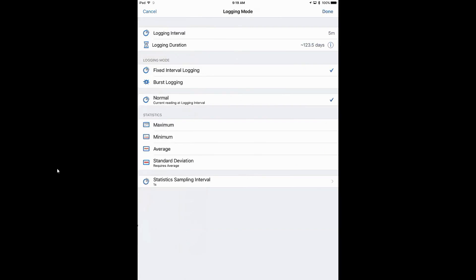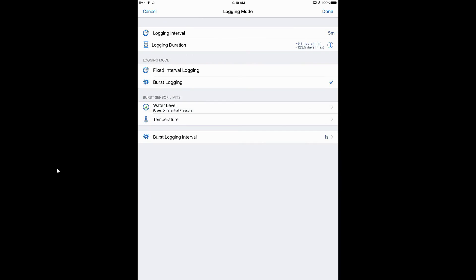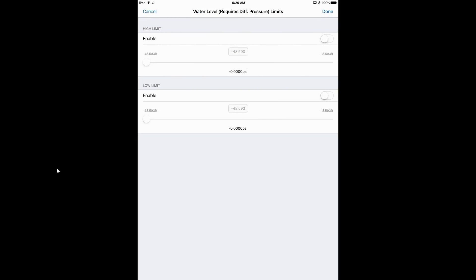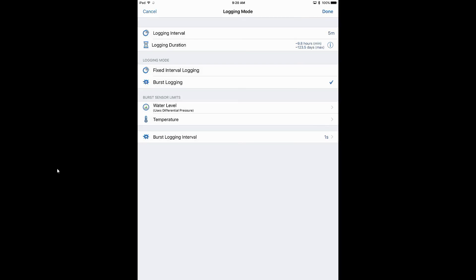We can select the logging mode: fixed interval, burst, or statistical logging. Burst logging is event-triggered — it's basically an event-triggered change of logging interval. With a five-minute interval, the logger wakes up every five minutes, takes a measurement, and goes back to low power. If you select burst logging, you can set limits for water level or temperature. For example, if it goes above a specific pressure or temperature, you want it to start logging faster. This is good for capturing events at finer resolution. For this application, we're just going to leave it at a fixed five-minute interval.